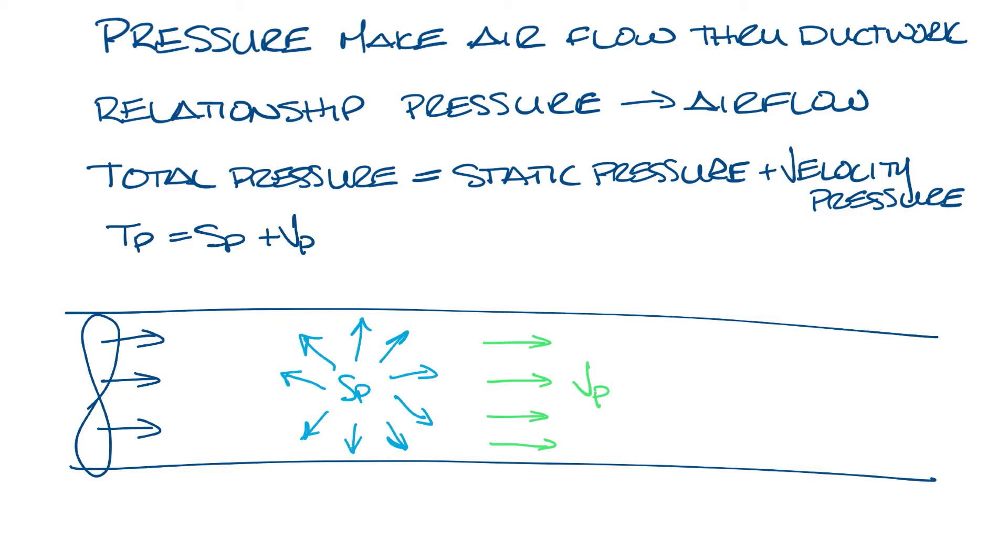The thing is, velocity pressure is hard to measure directly because there's static pressure in the direction of air flow as well, so we usually use total pressure and static pressure to calculate velocity pressure, or VP equals TP minus SP.